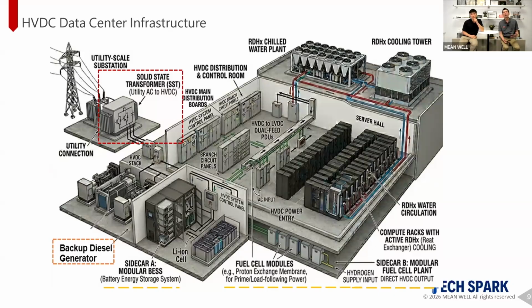For example, Andrew mentioned earlier about the solid state transformer. It's called a transformer, but it doesn't have any coil or anything like that—it's basically an AC to DC converter. It still has a lot of power electronics components in there that step down the three phases from AC down to 800 volt DC, and that 800 volt DC gets brought into the data center.